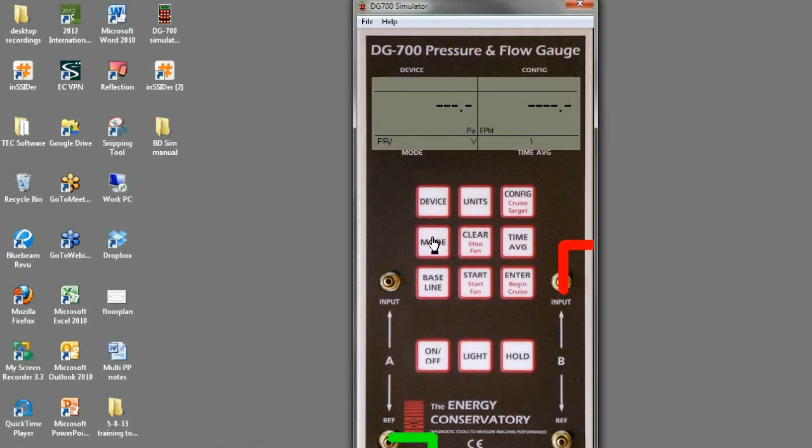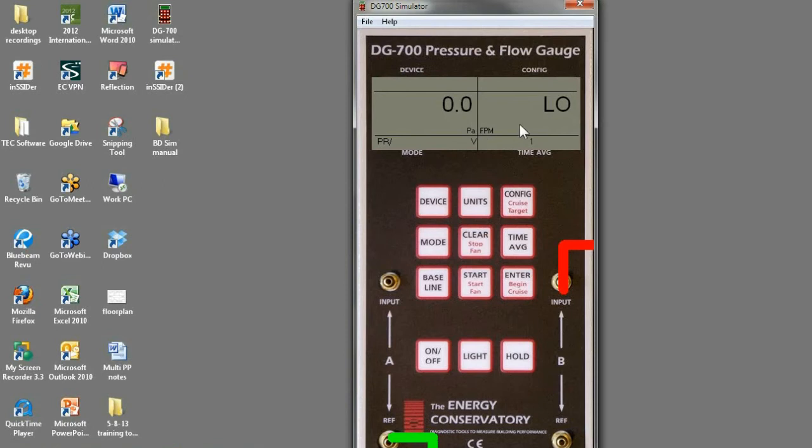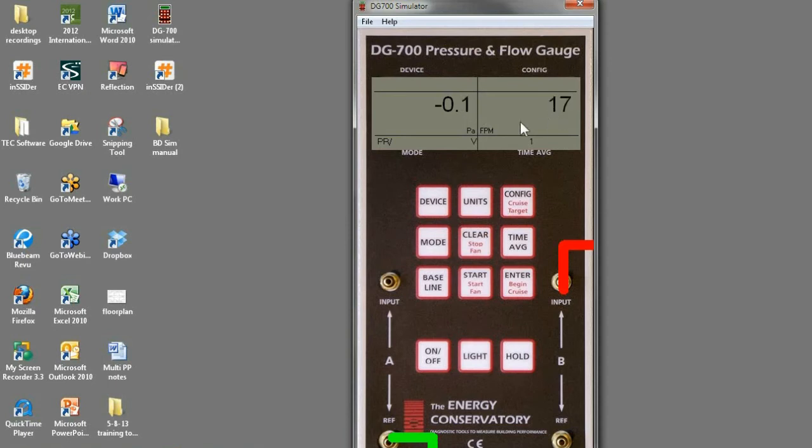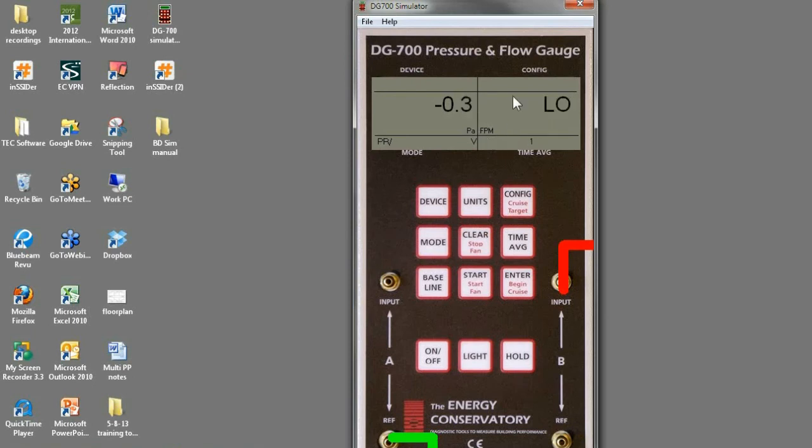I'm going to click one more time. Pressure velocity, PRV. So what this will do is if you're using a pitot tube, and a pitot tube has two taps on it. One will read static pressure, one will read total pressure, and the difference between total and static is velocity pressure. And this will convert velocity pressure in pascals to velocity in feet per minute.